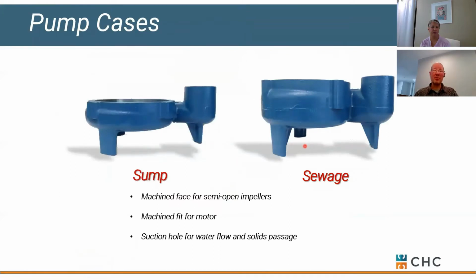We have a lot of manufacturers that will call their pumps sewage and sewage related or sewage applicable, and others will call them sump pumps. Some will just call them submersible, and it's up to you to figure out which ones you're going to use. It can be very confusing to figure out what pump you should be using. One thing to look at if you're new to sump and sewage is the thickness or depth of the case. If it's a relatively shallow case, it means you don't have a lot of room in there to pass high particulate or high solids, which you tend to see in sewage.